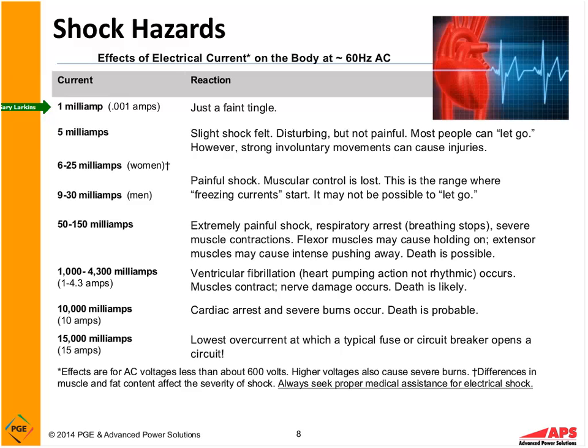So this is the level at a typical GFCI, ground fault circuit interrupter. If you were to look around your kitchen sink, hopefully you have these receptacles installed. They have 2 buttons on them. One's a push to test, one's a reset button. And by the way, these are designed to be tested monthly. But if those are installed properly, they are designed to trip between 0.004 to 0.006 amps of current, 4 to 6 milliamps. And that's this level, slight shock felt, disturbing but not painful.